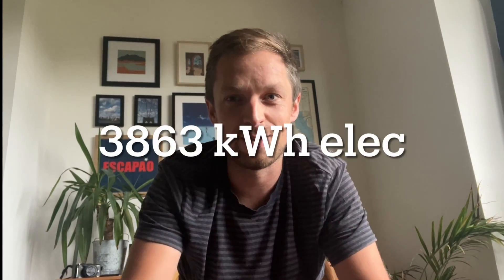Let's get straight to it. Our heat pump was commissioned two years ago on the 13th of July 2021. I took some readings last year on the 13th of July 2022 from our electricity meter and our heat meter connected to our unit — all the energy the system needs to power the heat generation but also pump water around our system. I missed the 13th of July this year because I was on holiday, but I got some readings a few days later. In the last year we've used 3,863 kilowatt hours of electricity to produce 12,171 kilowatt hours of heat. That's 137 kilowatt hours less electricity than the year before but 330 kilowatt hours more heat — we've used less but got more out.